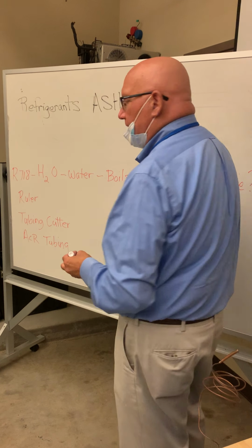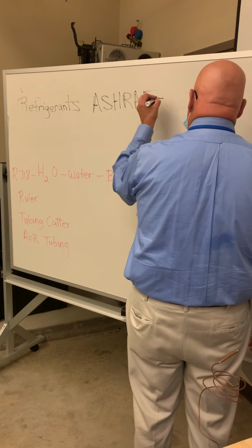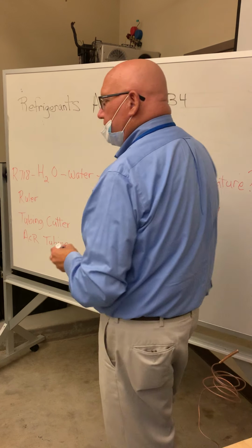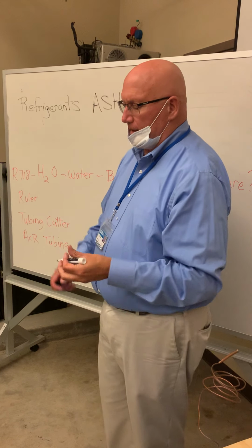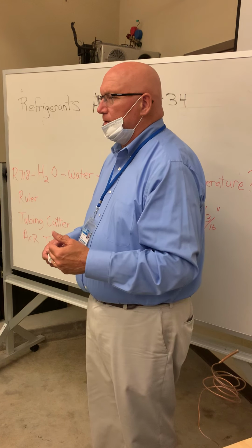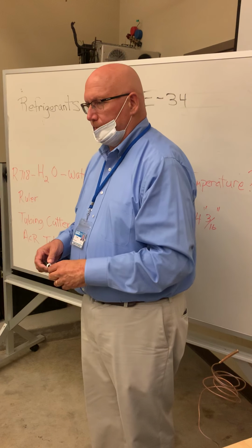They have a standard, and it's called ASHRAE Standard 34. So ASHRAE Standard 34 classifies refrigerants by toxicity level and flammability level.